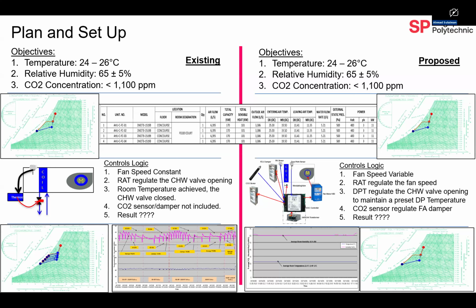That's why if you look on the right side, we have temperature control and humidity control. But in the air conditioning world, we do not control humidity directly, we use dew point control, because humidity, if you look at the unit, is in percentage, so it's relational to a certain number. If you have a relational number, it's very difficult to control directly, that's why we always use the dew point temperature.